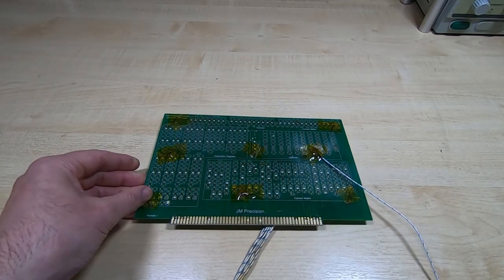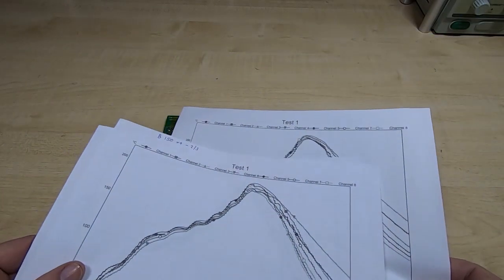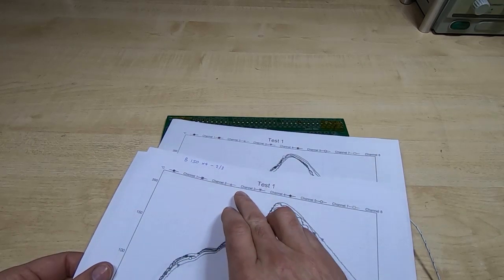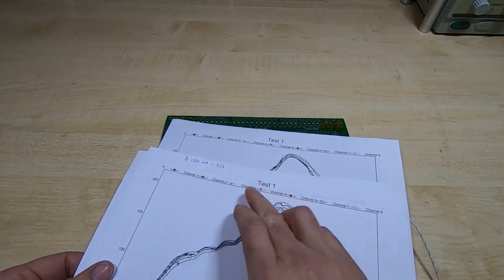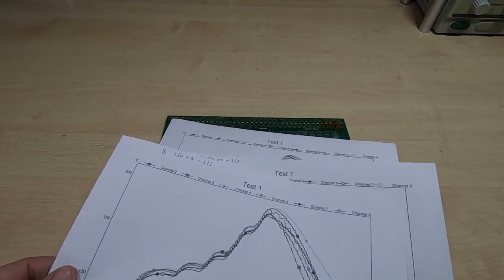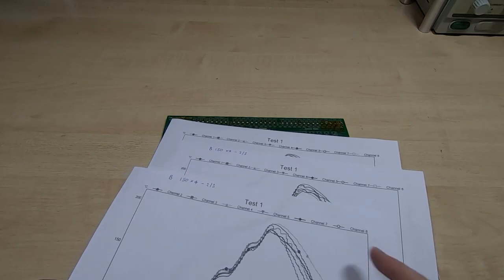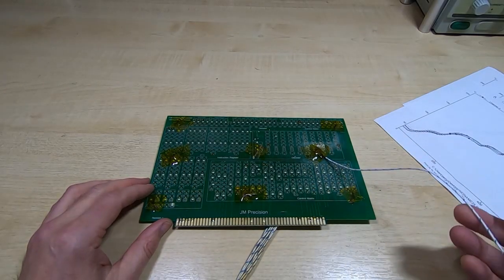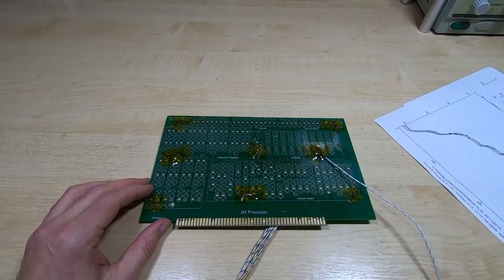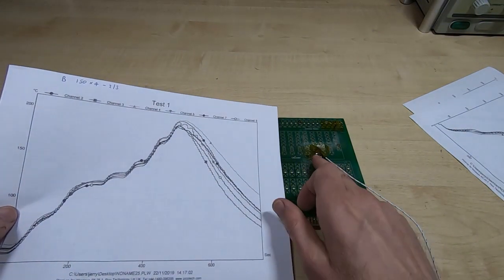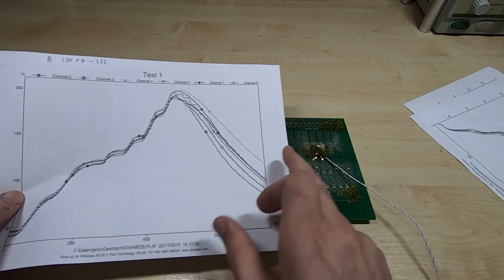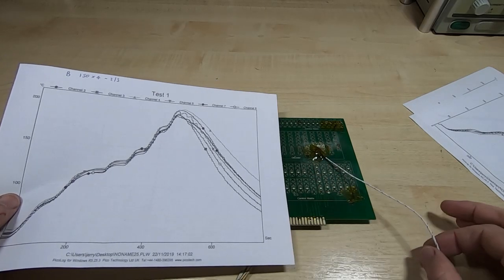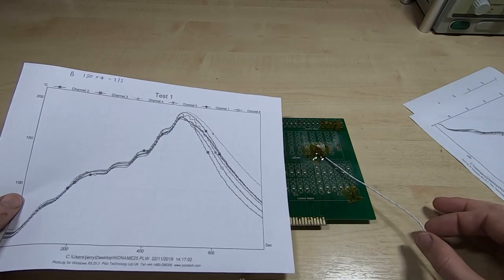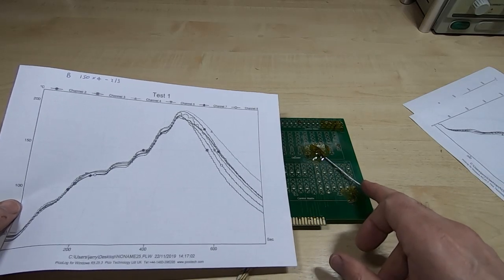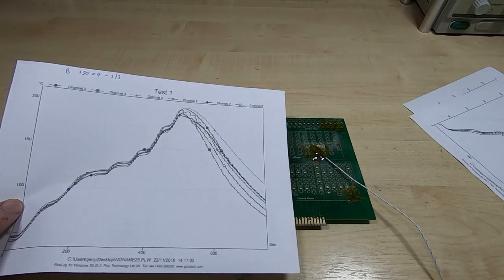Also along the way, any sharp-eyed viewers may have noticed that on various tests not all the channels are always showing. So if we look on this particular test, in which case they are all showing, if we look at another one, we'll see that in this case channel 6 is not showing. And the reason for this is because on each run I insert a separate reference probe, and I will then get two sets of data for the same location. I'll get one from the probe that's permanently attached to the board, and I'll get a separate trace for this additional probe. What I'm looking for is to make sure that the additional probe, which I calibrate more frequently, is giving the same response as the probe on the board.